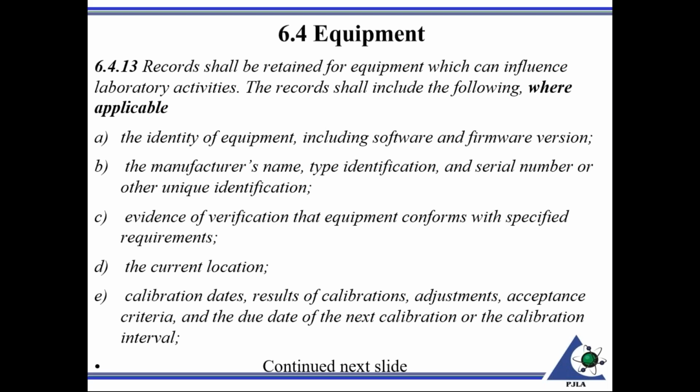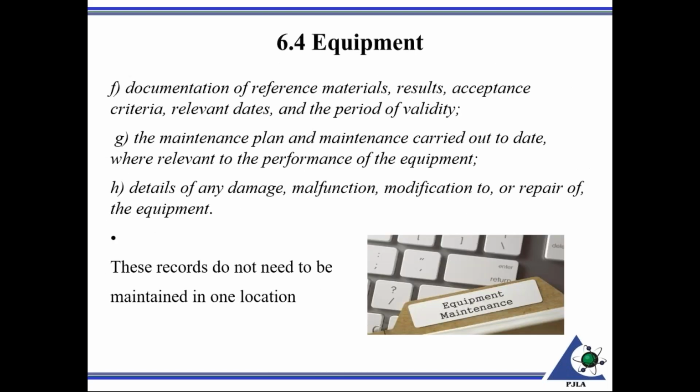Of course, you want to keep the calibration results, those reports, the calibration dates, results, any adjustments, assuring that the equipment met the accepted criteria, and the due date of the next calibration. We have a calibration program recall, so we want to keep a record of when the next time the equipment would be due for calibration.